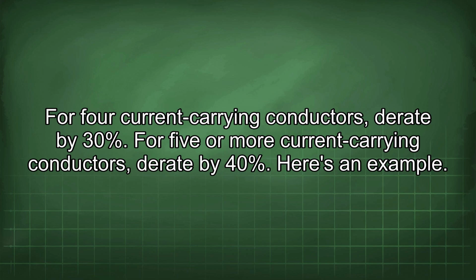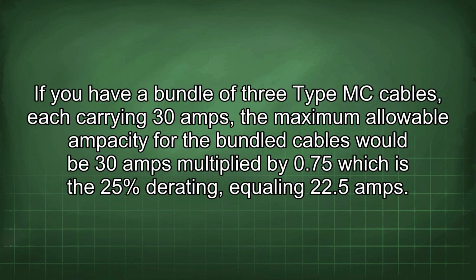Here's an example. If you have a bundle of 3 Type MC cables, each carrying 30 amps, the maximum allowable ampacity for the bundled cables would be 30 amps multiplied by 0.75, which is the 25% derating, equaling 22.5 amps.